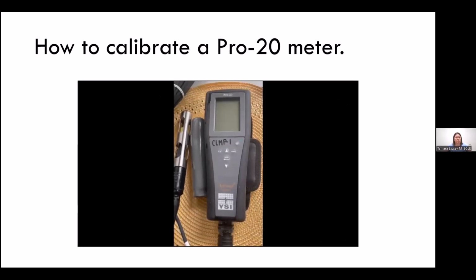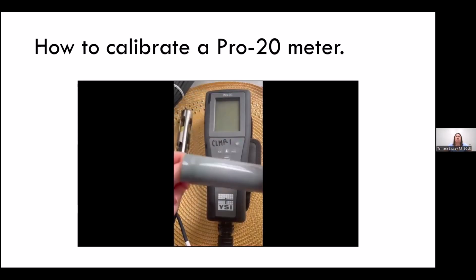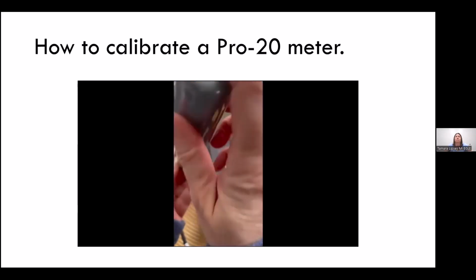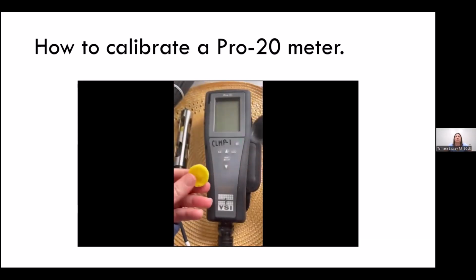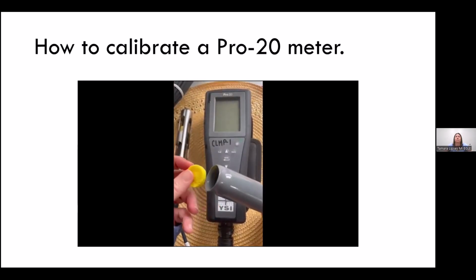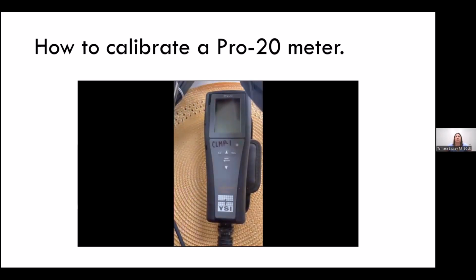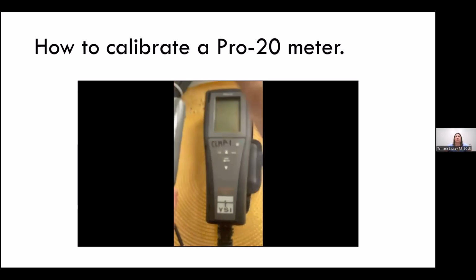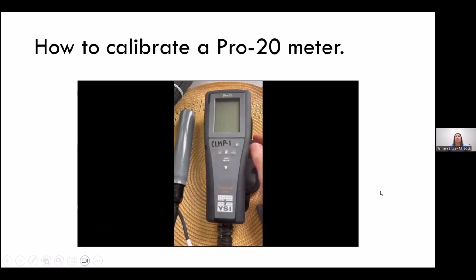This video is to show you how to calibrate your YSI Pro 20 dissolved oxygen and temperature meter. It's really pretty simple. First, you want to check inside the cap that covers your probe and make sure that the sponge that's inside is wet. Always want to keep the environment for the DO probe moist, but it shouldn't be standing water. You just put that back on and then turn the unit on.